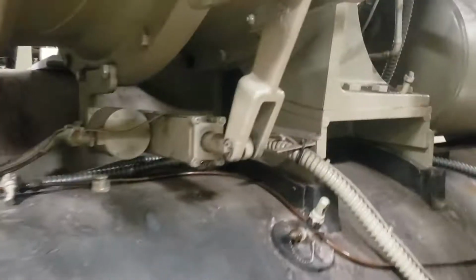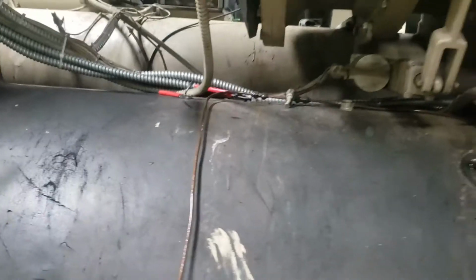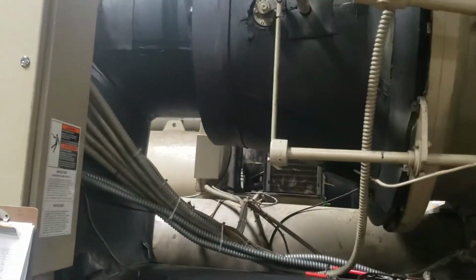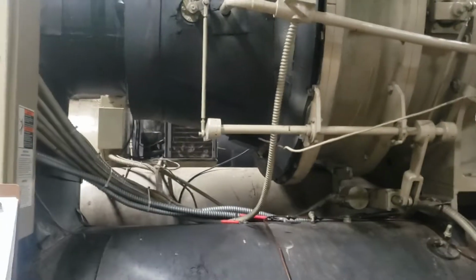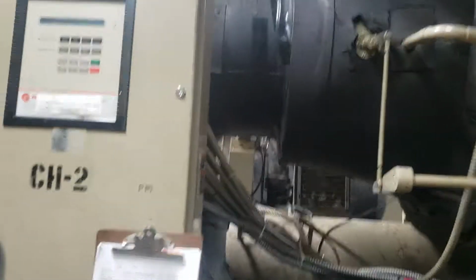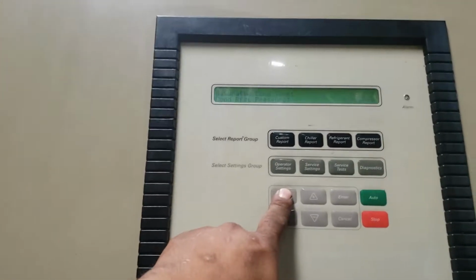Now it more likely seems like there's a leak somewhere in the low side of this chiller. I'm saying it's the low side because it's still sucking in air while it's running. This is a low pressure chiller. When this chiller is running, your condenser will be in a positive pressure, maybe 3 psi. We'll show you right here. Condenser is 2.9 psi, so you know you're not sucking in air. You're not under a vacuum when it's running.